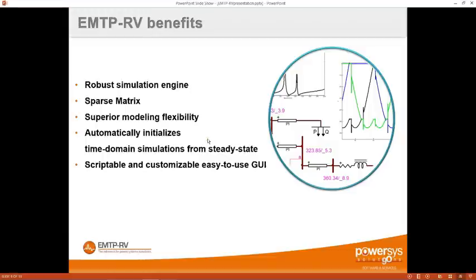We also have automatic initialization of the time domain simulation. Most of the time, for machines, you have information about power, voltage, and the angle of the voltage, but you don't know the rotor angle at t=0. In EMTP, you set all power constraints, run the load flow, and during the steady state solution the power angle of each machine is initialized and the field voltage is calculated. So the simulation starts with no initial transient.